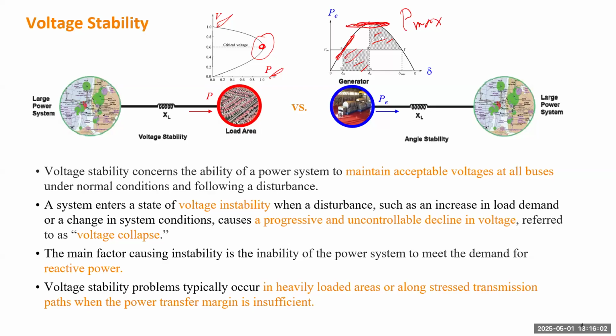Voltage stability problems typically occur in heavily loaded areas or along stressed transmission paths when the power transfer margin is insufficient. So to study voltage stability, you don't really need a very detailed generator model. For some systems, you don't need to model the generator at all. That's why the power flow equation may be enough. What we need is the topology near that load area. Then we develop the PV curve, and based on that PV curve, we can tell when the voltage collapse can happen. Definitely in many real cases, we also need to consider dynamics, and then we'll need the dynamic model.